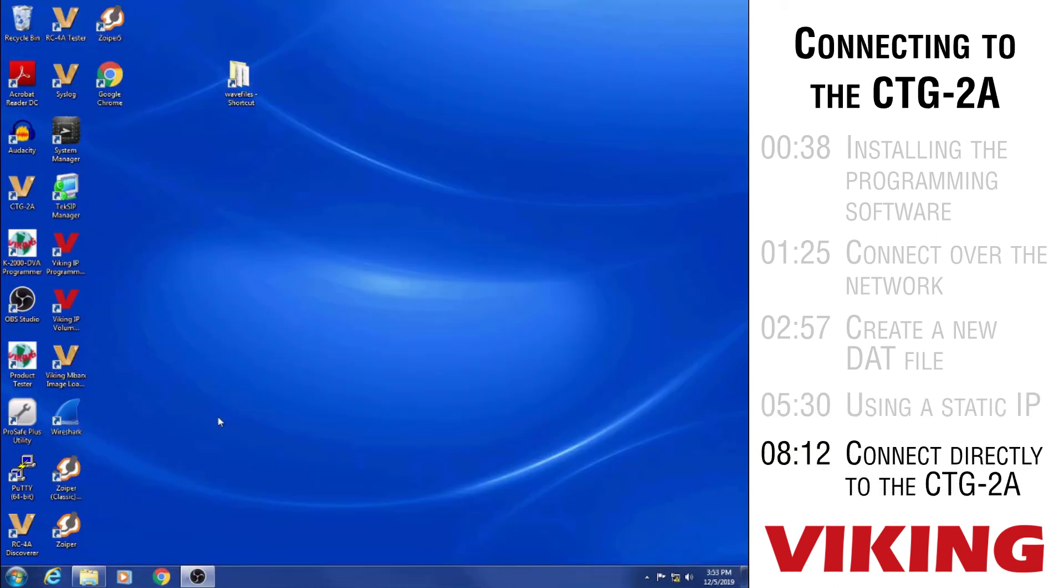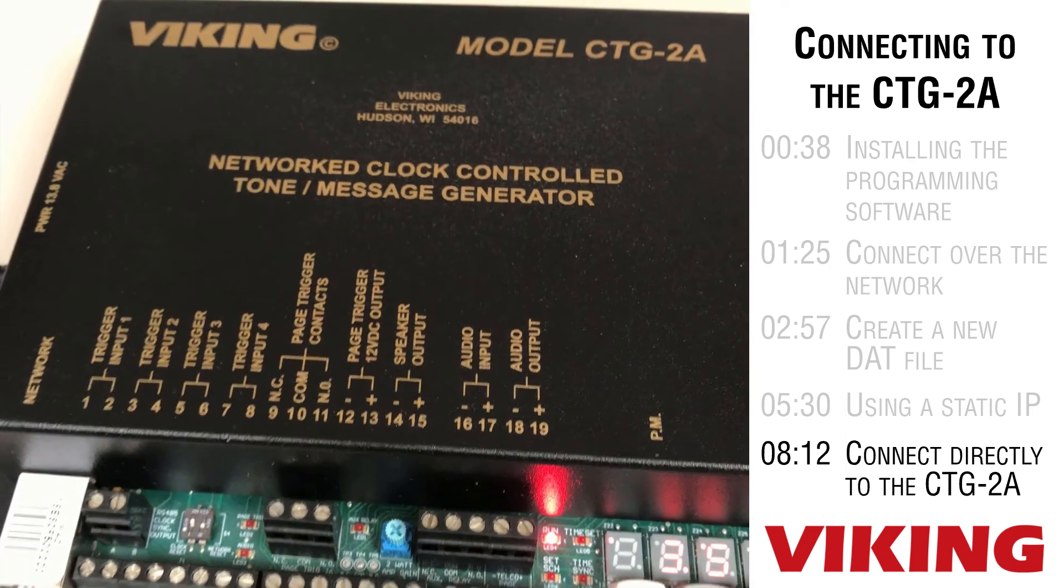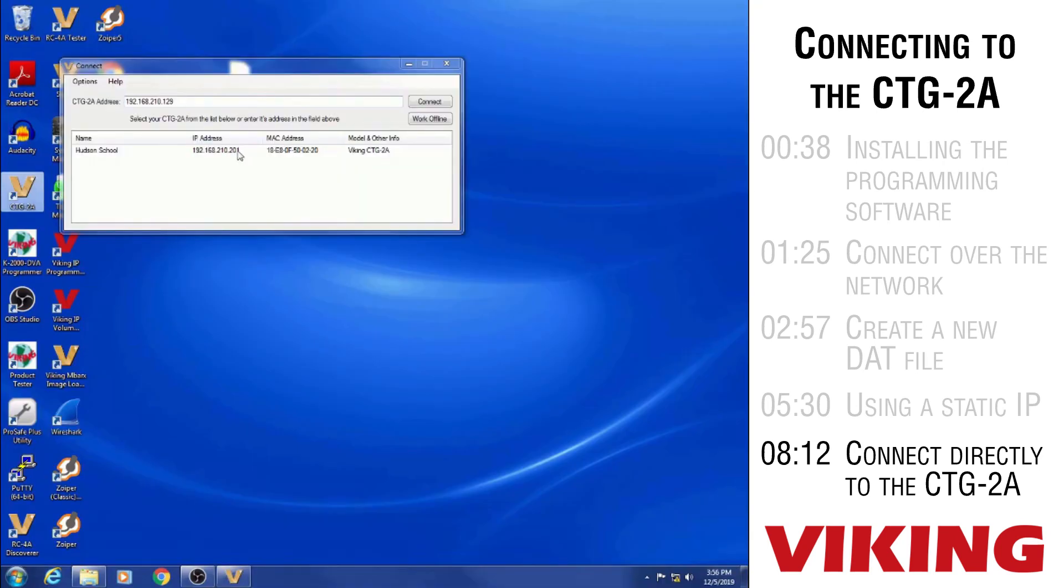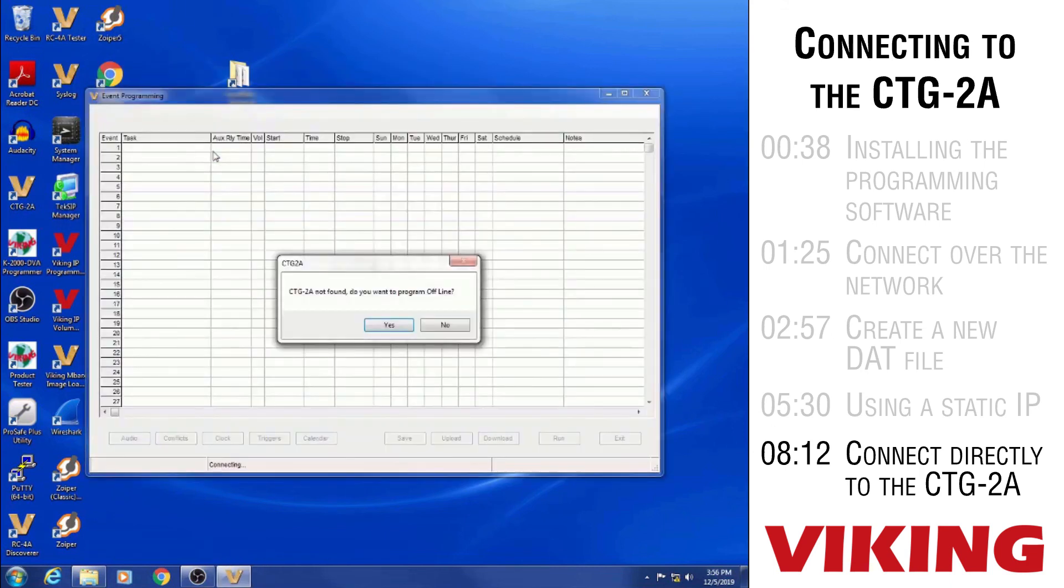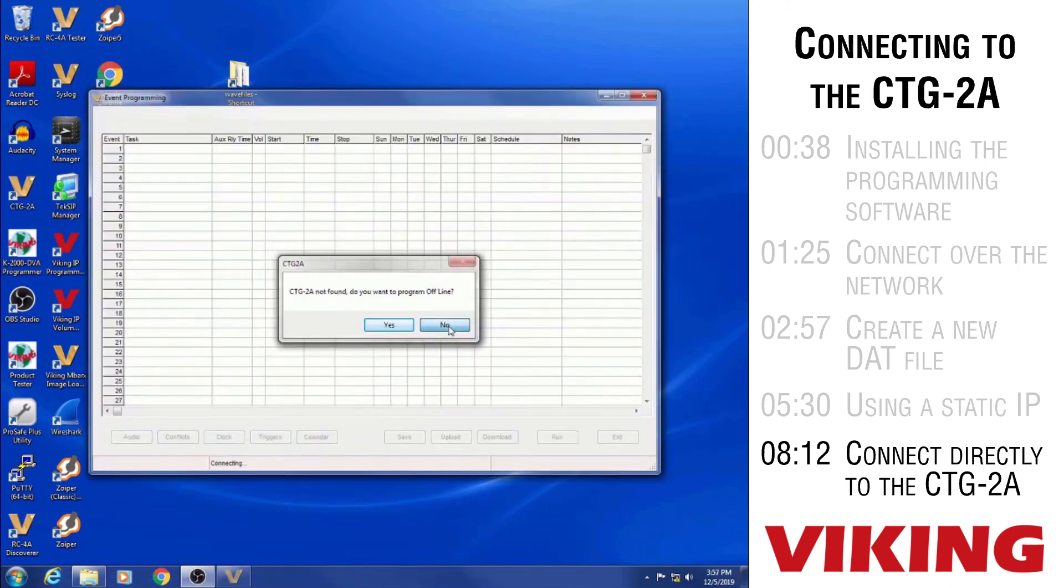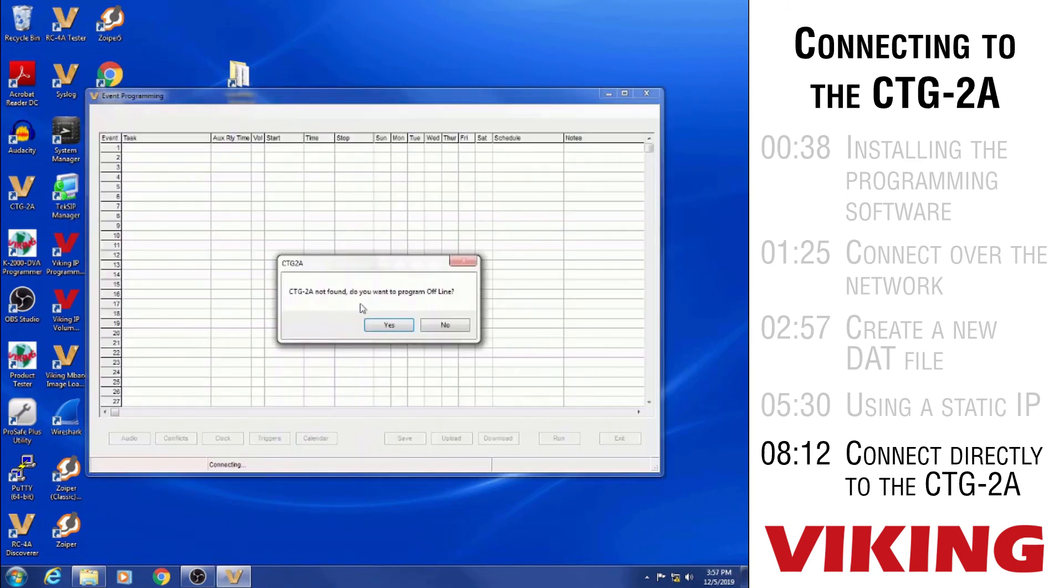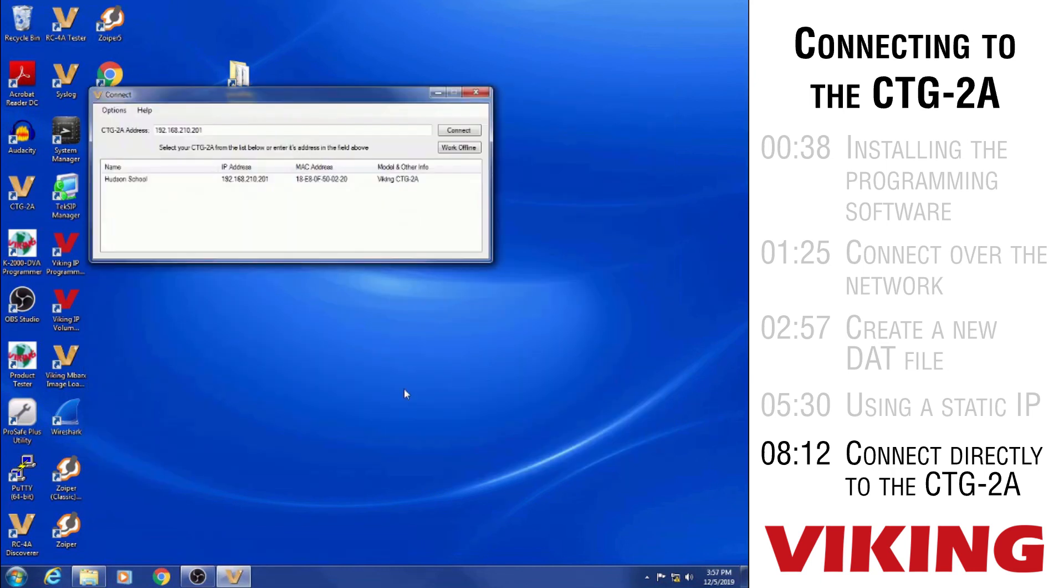Everything that we've done so far both the computer and the CTG-2A have been connected onto a computer network with each other. Now we have changed that so that just the computer is connected directly to the CTG-2A. You can see the CTG-2A is showing up with an IP address that is probably the last IP address that it had when we connected to it last. Let's just try connecting to it once and see how it says that the CTG-2A is not found. Asks if we want to program offline. That's very common when you're doing a direct connection like this. You would quite often get a message like this because the IP address of the computer is not within the same range as the IP address of the CTG-2A. So they're just having trouble communicating with each other.